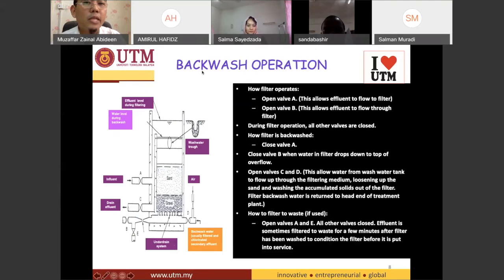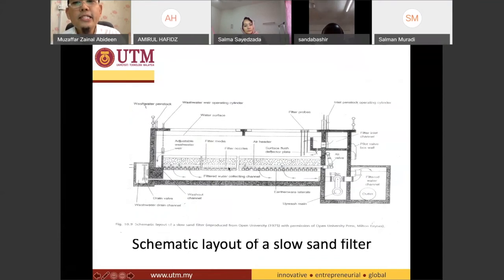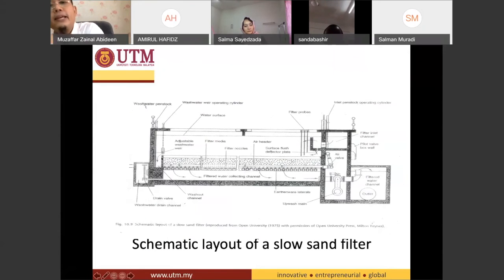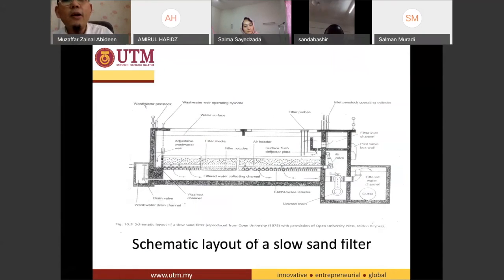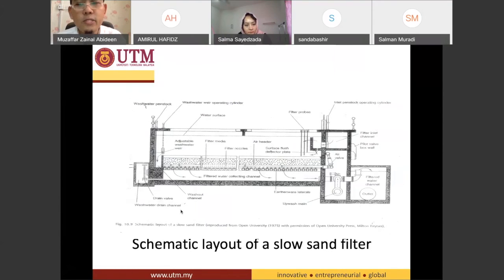The things I have explained are all printed on this side. For the slow sand filter, the water travels through the filter and goes out. Instead of doing the backwash method, they scrape the upper layer of the filter, take out that sand and gravel, and replace it with new sand or gravel. They don't practice the backwash method — that is how they clean the slow sand filter.